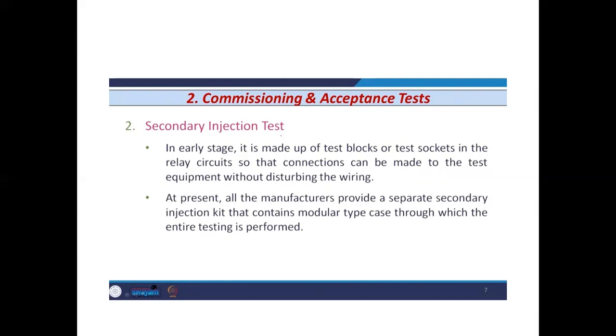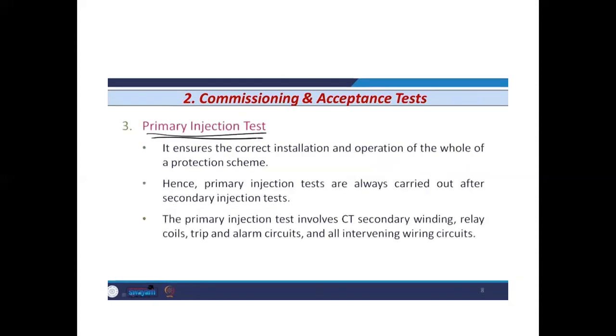Okay, so that the remaining wire is not disturbed. The third one is the primary injection test. It ensures the correct installation and operation of the whole of the protection scheme. Hence, primary injection tests are always carried out after the secondary injection test. So keep in mind that first we have to perform the secondary injection test, followed by the primary injection test.